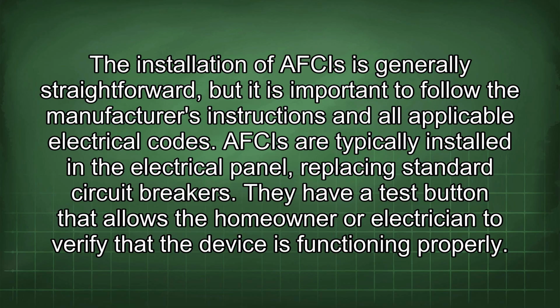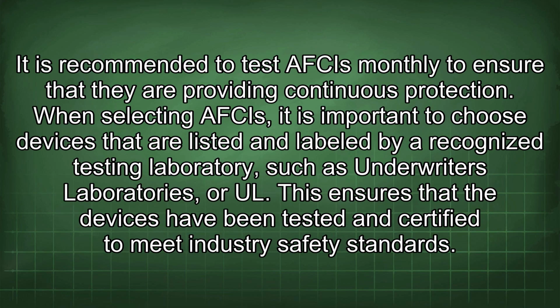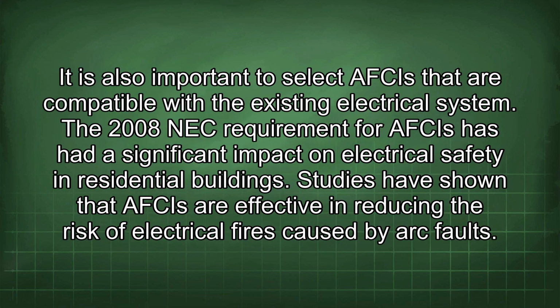The installation of AFCIs is generally straightforward, but it is important to follow the manufacturer's instructions and all applicable electrical codes. AFCIs are typically installed in the electrical panel, replacing standard circuit breakers. They have a test button that allows the homeowner or electrician to verify that the device is functioning properly. It is recommended to test AFCIs monthly to ensure that they are providing continuous protection. When selecting AFCIs, it is important to choose devices that are listed and labeled by a recognized testing laboratory such as Underwriters Laboratories or UL. This ensures that the devices have been tested and certified to meet industry safety standards. It is also important to select AFCIs that are compatible with the existing electrical system.